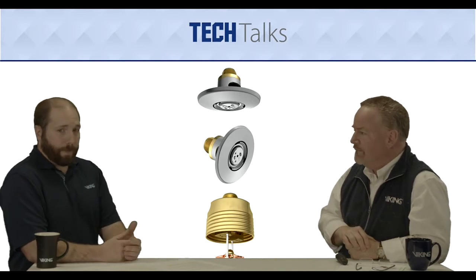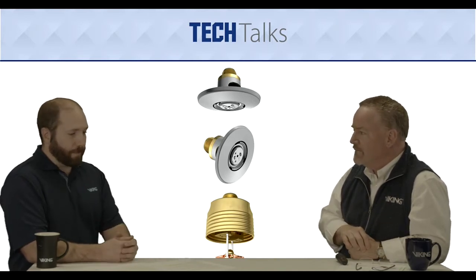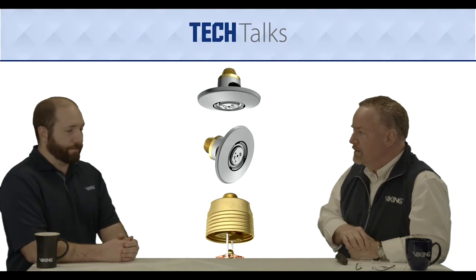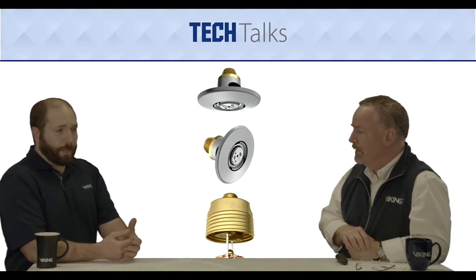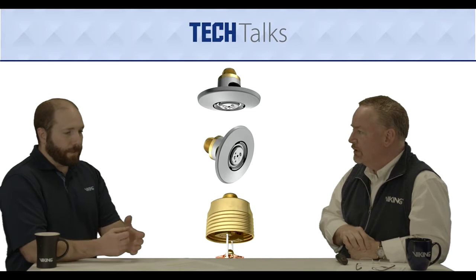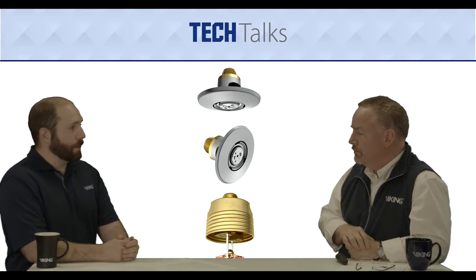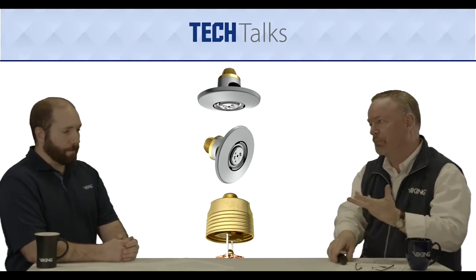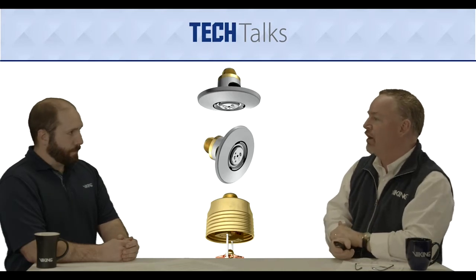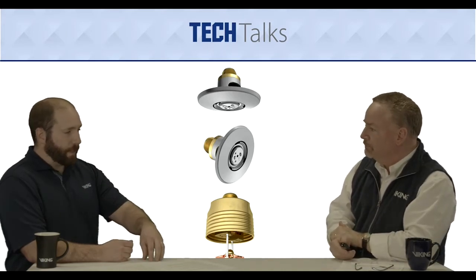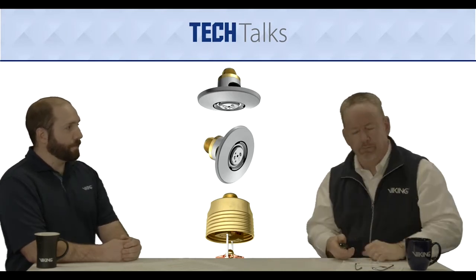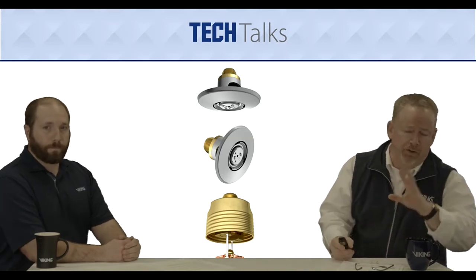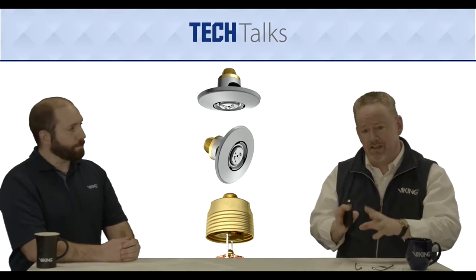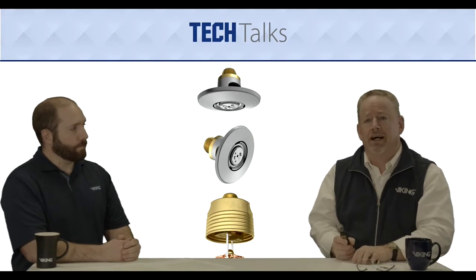Yeah, it's going to be evaluated under the exact same standard spray sprinkler different tests. The only thing different about it is it's using different materials to make it non-ferrous. Right, to make it non-ferrous and make it safe to use in places like MRI units. Yep, but its fire protection doesn't change. Right.